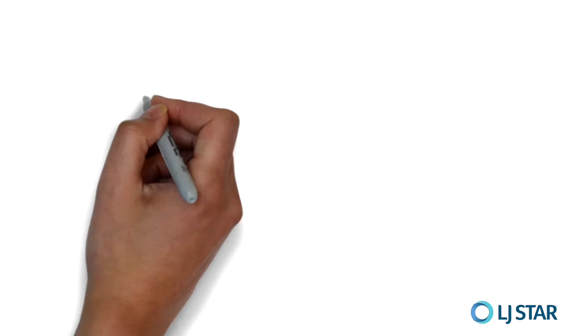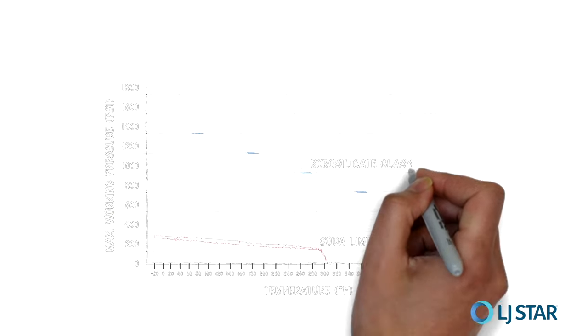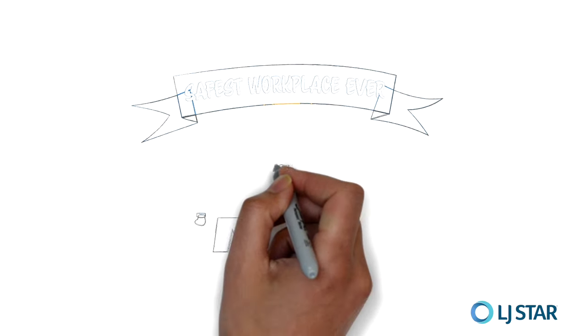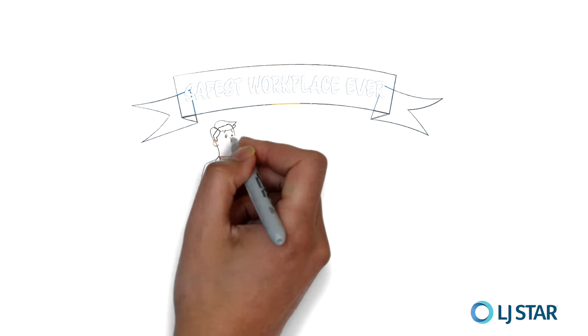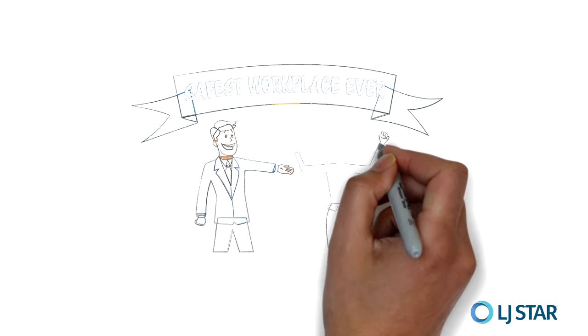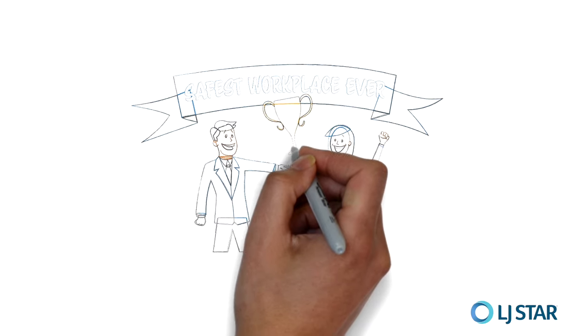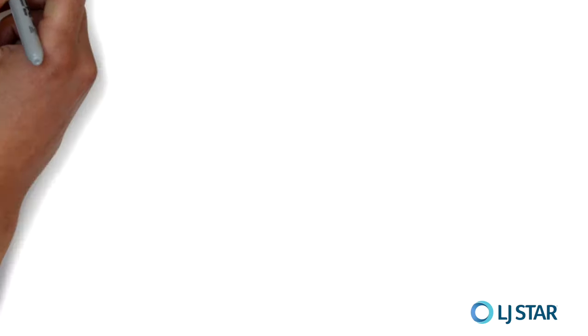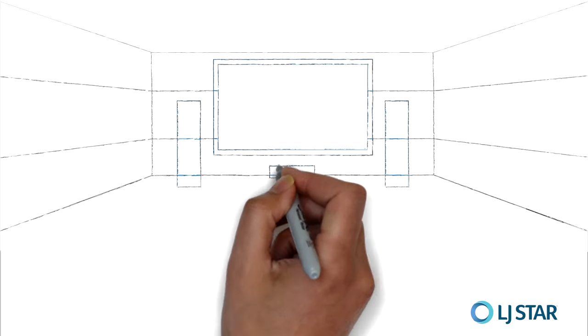There are other factors to consider: abrasion, corrosion, impact resistance. But here's what you need to remember — at higher temperatures and pressures, borosilicate glass will always outperform glass with any presence of soda lime, at every point on this chart. If soda lime isn't safe enough to go into your oven, why should you risk your industrial process and people to a sight window with soda lime?